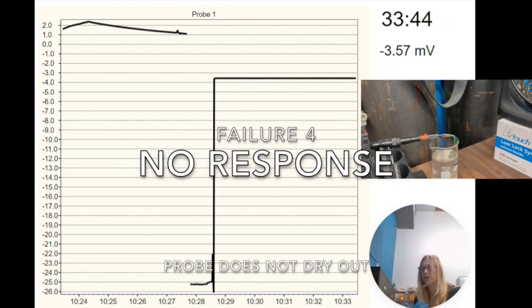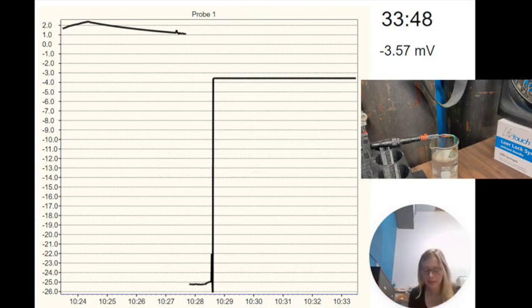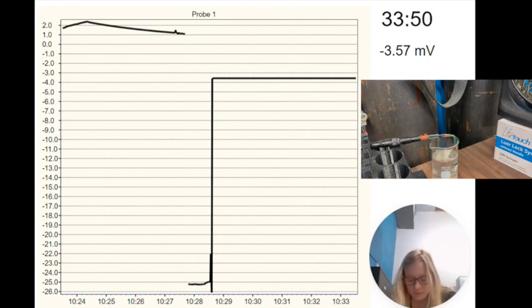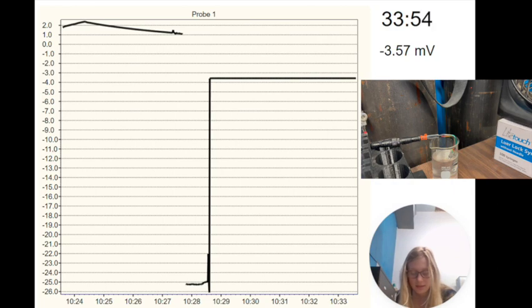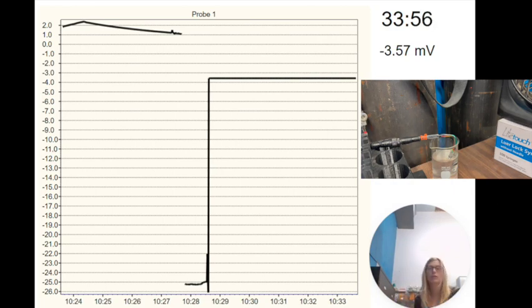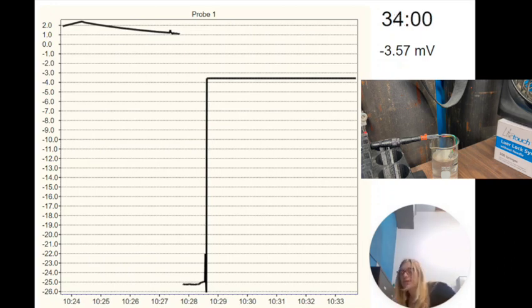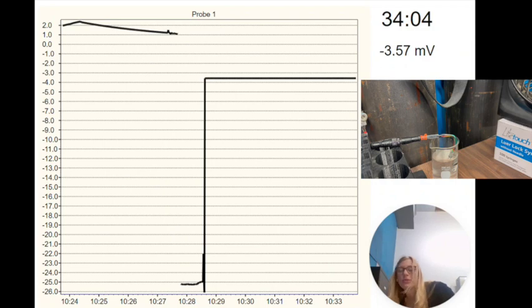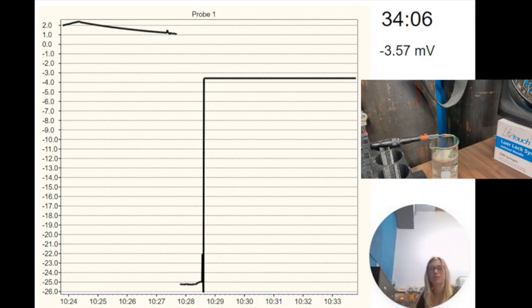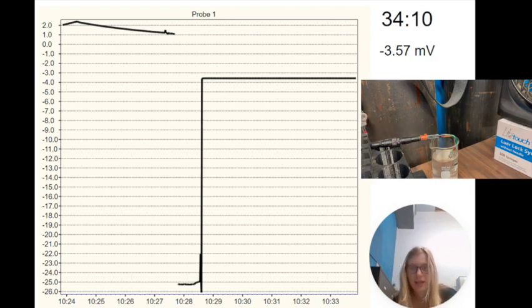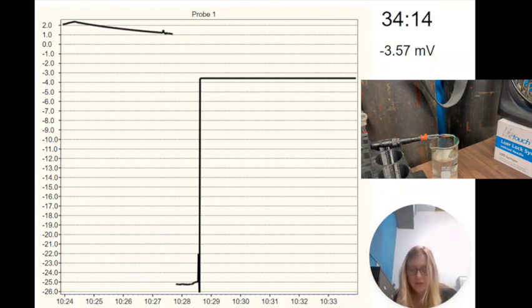Okay, so the last sensor type that I want to show is a no response. A variety of things can cause a no response sensor. Either pores or tube blocks for it to respond, or there's some damage, or it's cavitated. So they're important to identify and troubleshoot. So I have this probe C100 that's reading at minus 3.57 millivolts.